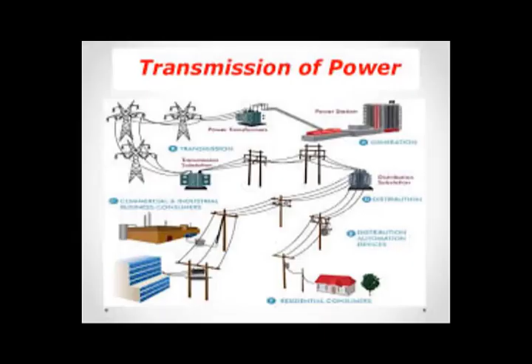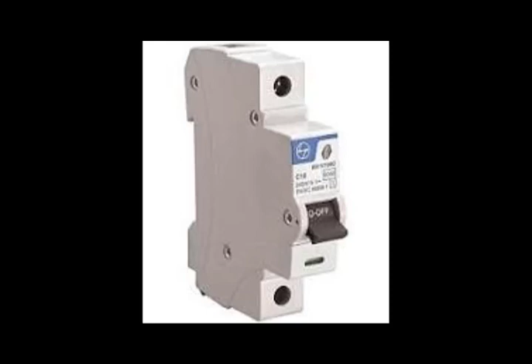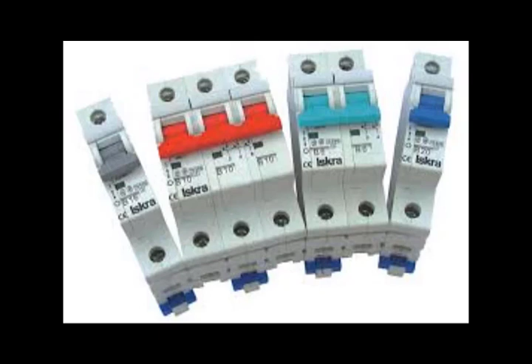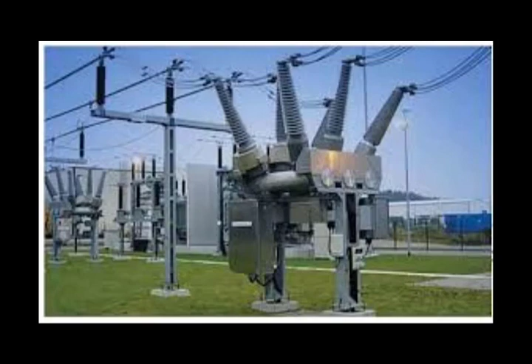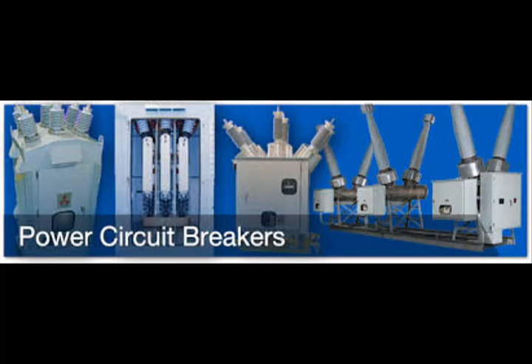Right from generation through transmission to distribution end, the current interruption devices are called circuit breakers. The circuit breakers can be operated manually as and when required, and they can also be operated automatically during overcurrent, short circuit or any other faults in the system by sensing the abnormality of system parameters. These power system parameters can be current, voltage, frequency, phase angle. The circuit breaker senses the faulty condition of the system through protection relays, and these relays are actuated by the faulty signal normally coming from the current transformer or voltage transformer.